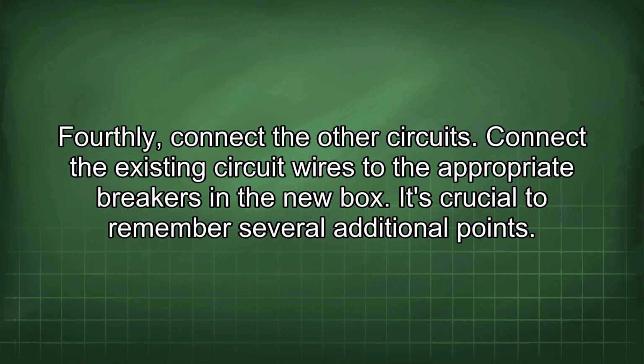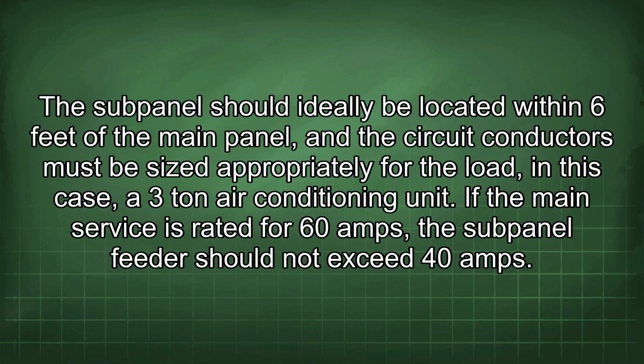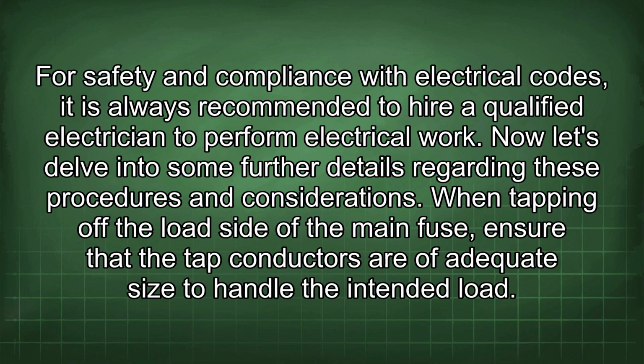It's crucial to remember several additional points. The subpanel should ideally be located within 6 feet of the main panel, and the circuit conductors must be sized appropriately for the load, in this case, a 3-ton air conditioning unit. If the main service is rated for 60 amps, the subpanel feeder should not exceed 40 amps. For safety and compliance with electrical codes, it is always recommended to hire a qualified electrician to perform electrical work. Now let's delve into some further details regarding these procedures and considerations.